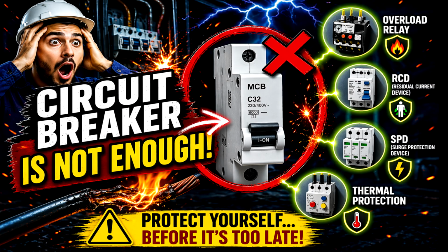Fifth type, thermal protection. Built into many devices and motors, if temperature rises beyond a safe limit, it automatically shuts down the system. Very important to prevent slow burning damage. Sixth type, advanced: phase monitoring or sequence relay. Important in three-phase systems. It protects against phase loss, phase reversal, and voltage imbalance. These can destroy motors quickly. In summary, if you only have a circuit breaker, you are protecting only a small part of the system. But if you combine all these systems, you build a complete protection system. Electricity doesn't joke. Either you understand it and protect yourself, or you wait for the mistake and pay the price.